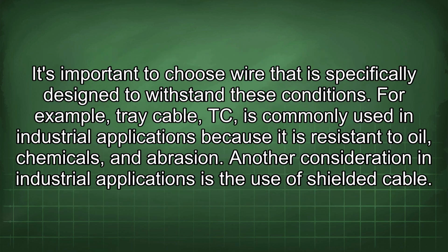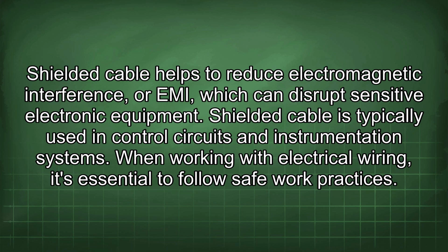It's important to choose wire that is specifically designed to withstand these conditions. For example, tray cable (TC) is commonly used in industrial applications because it is resistant to oil, chemicals, and abrasion. Another consideration in industrial applications is the use of shielded cable. Shielded cable helps to reduce electromagnetic interference, or EMI, which can disrupt sensitive electronic equipment. Shielded cable is typically used in control circuits and instrumentation systems.